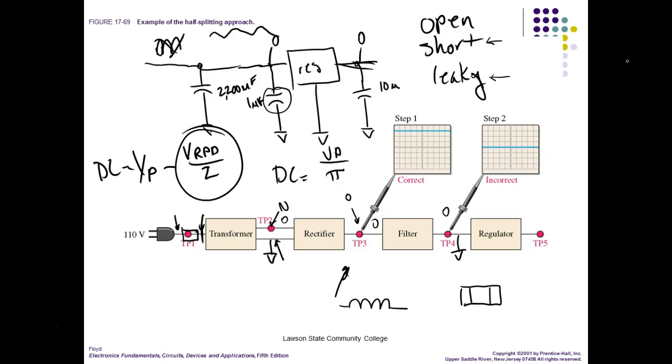Resistors are a little different in that they either open or the resistance goes up. I've never seen a resistor short. I've seen resistors be shorted around. Somebody screws up and shorts around the resistor, like with a meter.